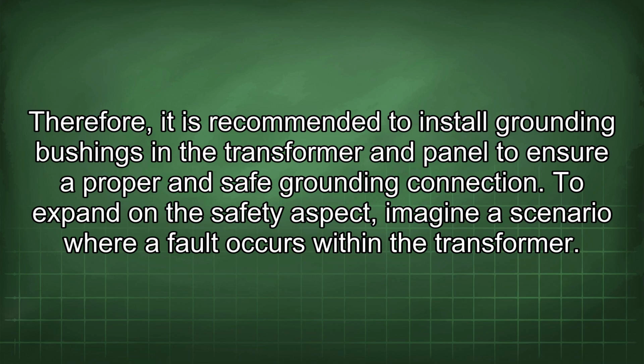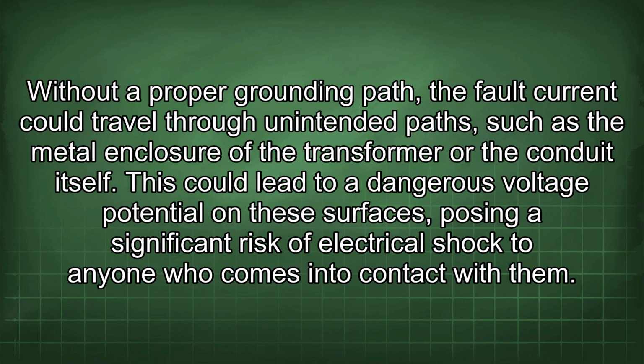connection. To expand on the safety aspect, imagine a scenario where a fault occurs within the transformer. Without a proper grounding path, the fault current could travel through unintended paths, such as the metal enclosure of the transformer or the conduit itself. This could lead to a dangerous voltage potential on these surfaces, posing a significant risk of electrical shock to anyone who comes into contact with them.